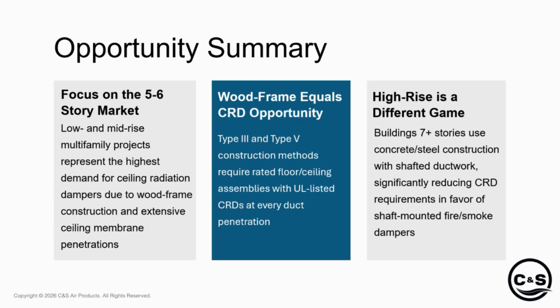So most contractors and engineers see that and think, well, the cheaper thing to do would probably be a dynamic radiation damper at that spot, instead of spending money on the fire stop device for the unit. So they started requiring dynamic ceiling radiation dampers. But the caveat is that a lot of these designs that they're testing and constructing are actually still static systems. So there's no caveat of just having a dynamic ceiling radiation damper at the unit. You have to put a dynamic ceiling radiation damper at every opening in the entire system, and you have to change the design of the building.